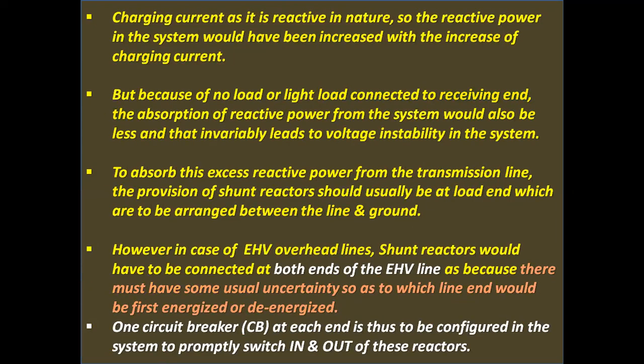Charging current, as it is reactive in nature, increases the reactive power in the system as the charging current increases. But because of no load or light load connected to the receiving end, the absorption of reactive power from the system would also be less, and that invariably leads to voltage instability in the system. To absorb this excess reactive power from the transmission line, shunt reactors should usually be provided at the load end, arranged between the line and ground.